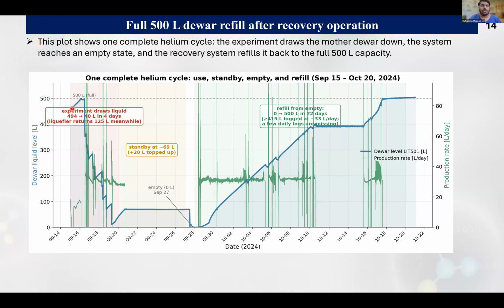We can see how we consume the liquid, starting from 500 liters and dipping down to 10 liters, then starting recovery from 10 liters back up to 500 liters. At this stage we were running experiments for about a week and consumed a lot of liquid, leaving only around 10 liters. After a couple of days we liquefy from gas back into liquid and return to 500 liters. Then we start our cycle again to do physics and reliquefy. That's the recovery system in our lab.